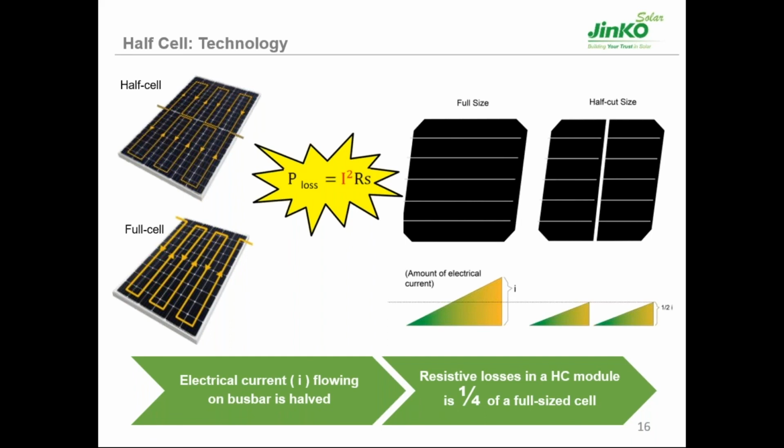Brilliant. Thank you very much. And one more question, again with the coefficient. Do you consider the module derating coefficient in your tool? Yes. Of course, I consider our line of derating. You can find the derating coefficient in all of our datasheets, and for every year in the 25 years, there is a derating coefficient in order to get the right lifetime energy output. So after the first year, where we have a certain derating coefficient depending on the technology, we will get the standard linear derating coefficient. And yes, the answer is yes.